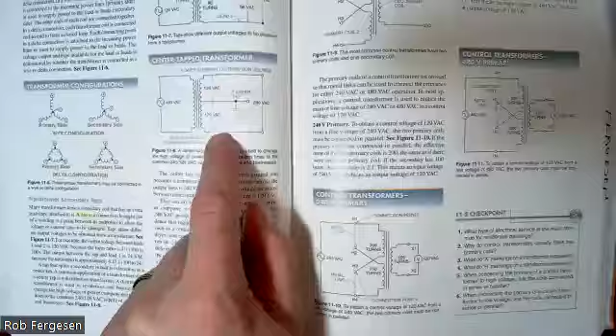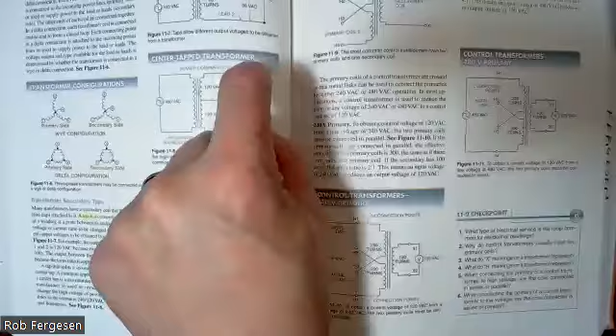For instance, a classic tapping arrangement: you might have a 480 volt input to a transformer, and on the output you might have the ability to get 240 volts if you attach to the ends of the coil, or you can get two separate 120 volt circuits, like a classic single phase residential application.